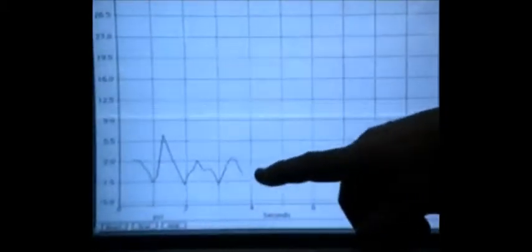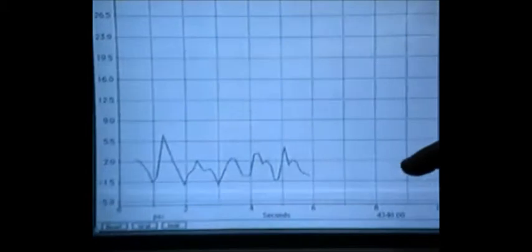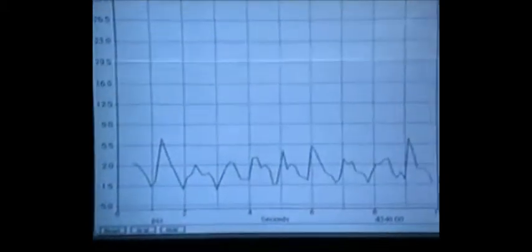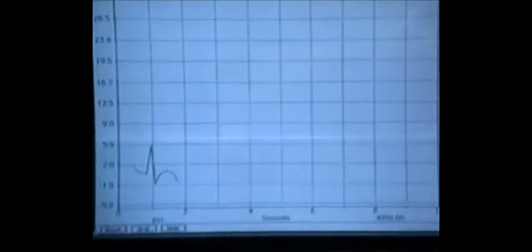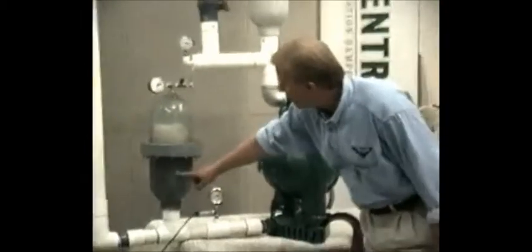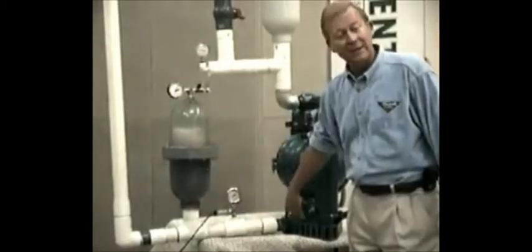Now if you notice on the transducer, the pressure spike has been absorbed by the inlet stabilizer and is now averaging around 2 psi. That amount of pressure spike is well within the limit of the air diaphragm pump and no damage will occur to its diaphragms. The valve balls will seat more positively. There's less chance of cavitation because we're accumulating liquid right at the inlet.